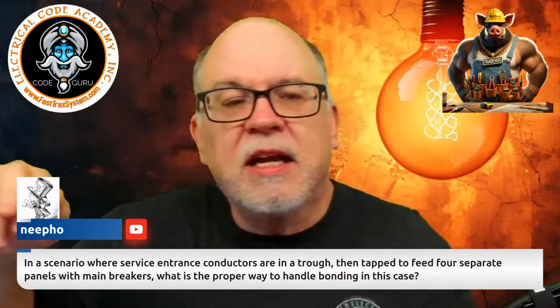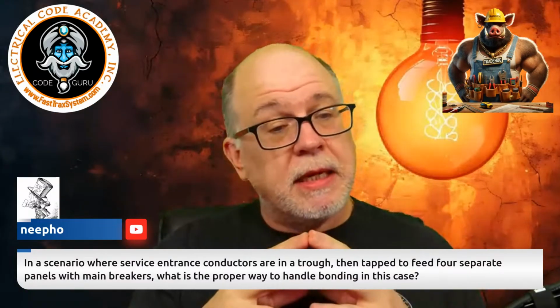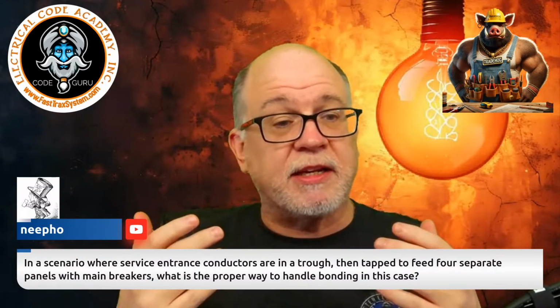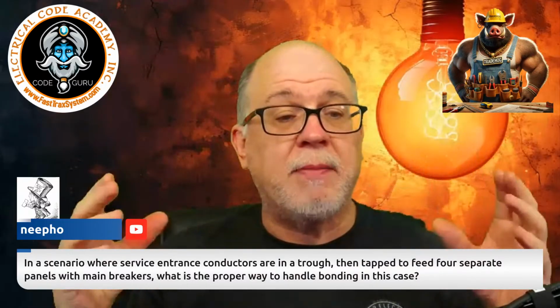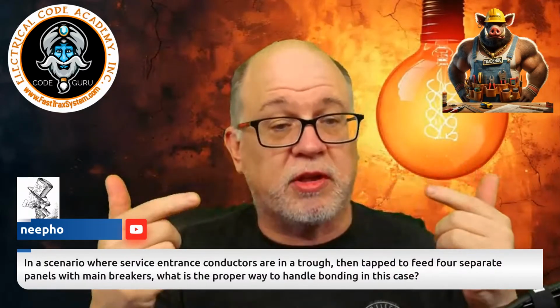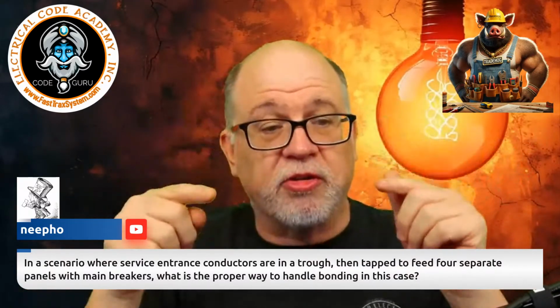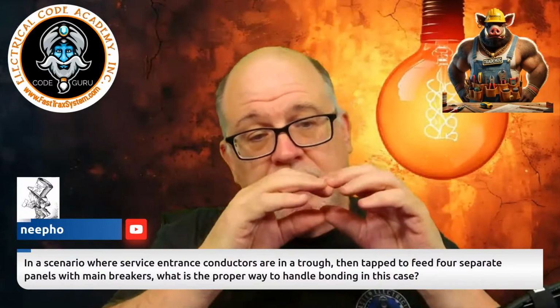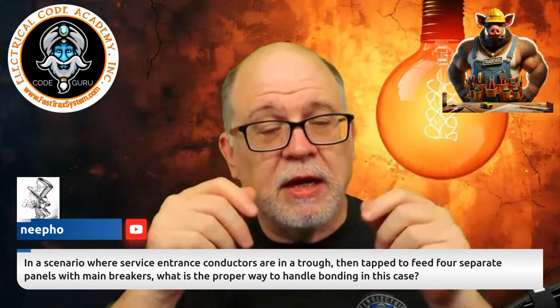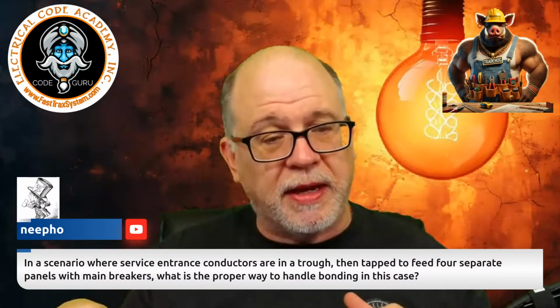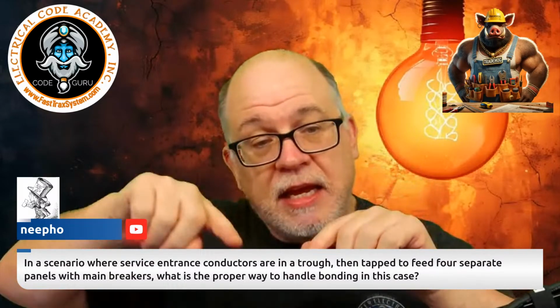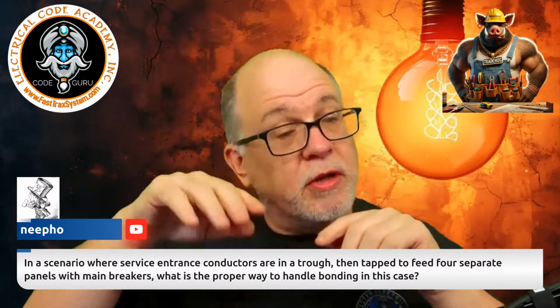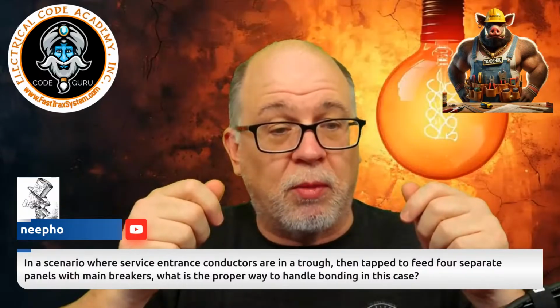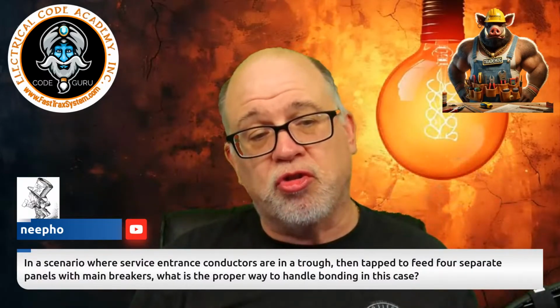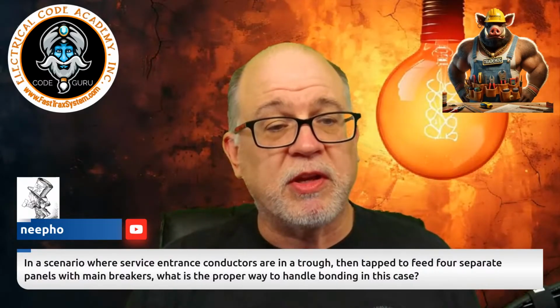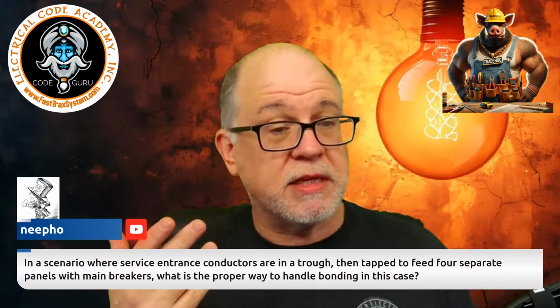The way to do that is to simply take your grounded conductors that come into the wireway, bring them to a lug connected to the enclosure, bring your grounded conductors into that lug, maybe multiple lugs, like a bar, and then come off of that and go to your panels. Bond to it, and usually if you mount it to the wireway, it's going to be all connected. So you can use your grounded conductor, and that is 250-142 to do that.